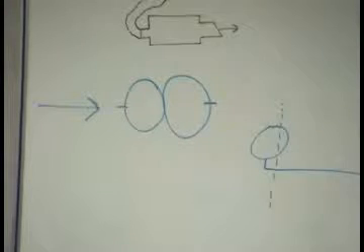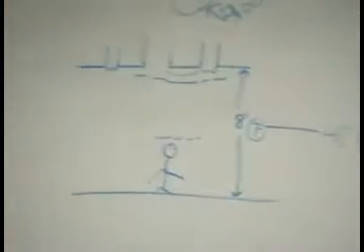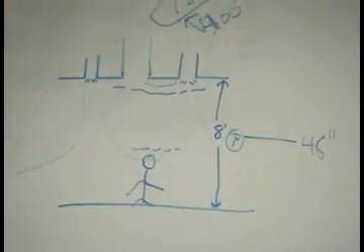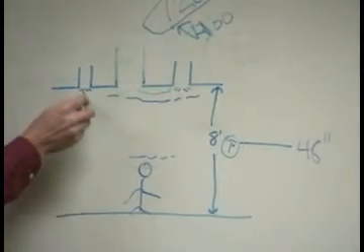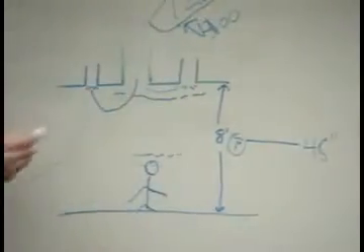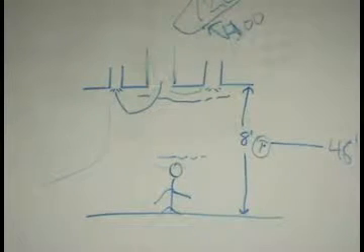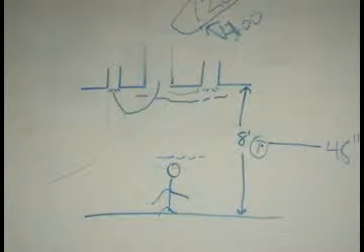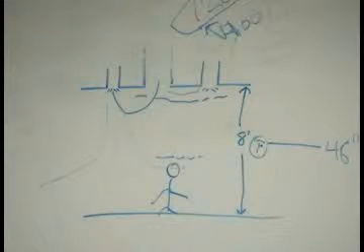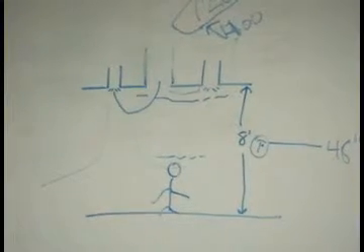The greater the temperature difference between the two streams of air, the harder it is going to be to mix them. The problem with this situation ever working is it's like rolling a ball uphill. Every time you roll it up, gravity wants to roll it right back, because the fan is pulling the air up, and you're trying to push the air down, and it's just going to want to come back up. So natural flow is going to be back up to the register, to the return grill.